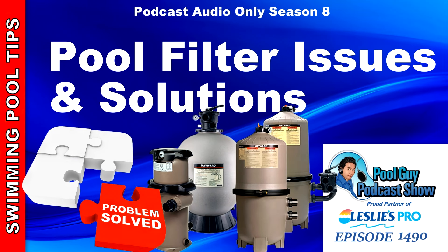Replace that filter if it cracks. I also would replace a single cartridge filter if it's starting to look really, really old. If you're having trouble getting the top off or trouble putting it back together, it's probably time to replace that filter — it's just pretty worn out, especially if there's a ring in the center that you have to spin to lock into place. Things don't last forever and you have to replace it. That would be my guideline for replacing the filter tank itself, not necessarily filter element problems.